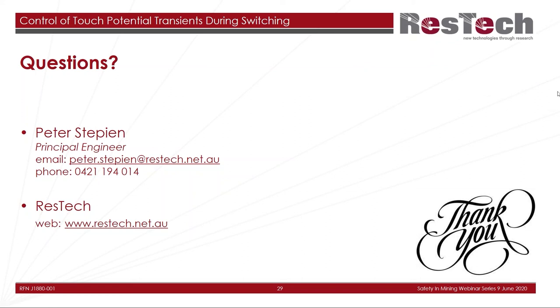Yes, so the question about the delay between switching. This is basically a three-phase contactor, so it's all one complete unit. Even being one complete unit with basically one driving coil to open and close them, there is still a delay between those phases. If you think about the construction of these contactors, there's a reasonable amount of play in the construction as well. You can see how you can get some delay between the contacts, and the fact that we've actually measured those delays in the field means that this is actually occurring. It's not just a theoretical idea.